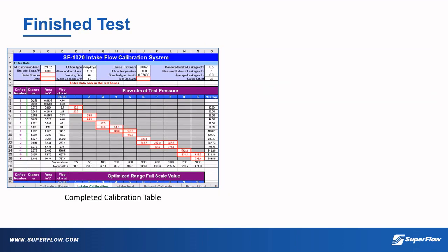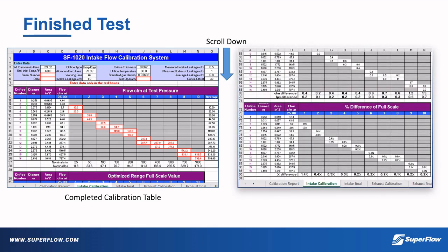Once every box along the diagonal is filled with the flow rates found during testing, the table is complete. Scroll down to the bottom of the page and look at the table labeled % difference of full scale. This is a measure of the calculated difference of the bench compared to what is expected. You will find these percentages along the bottom. The acceptable values here are as follows. Range 1 must be within plus or minus 2%, while all other ranges must be within plus or minus 0.5%. If any range falls outside of these % differences, there is a problem with the bench itself.